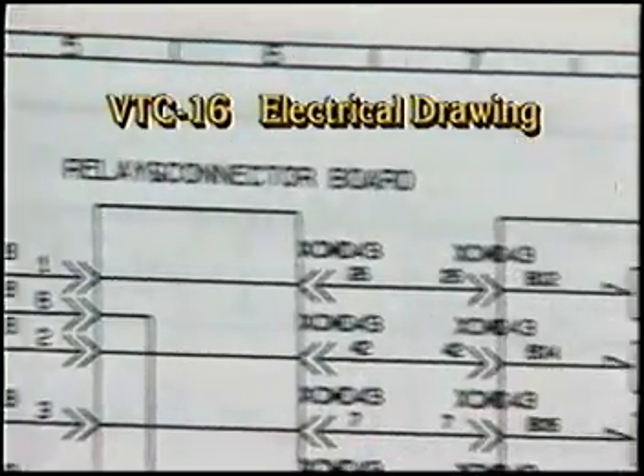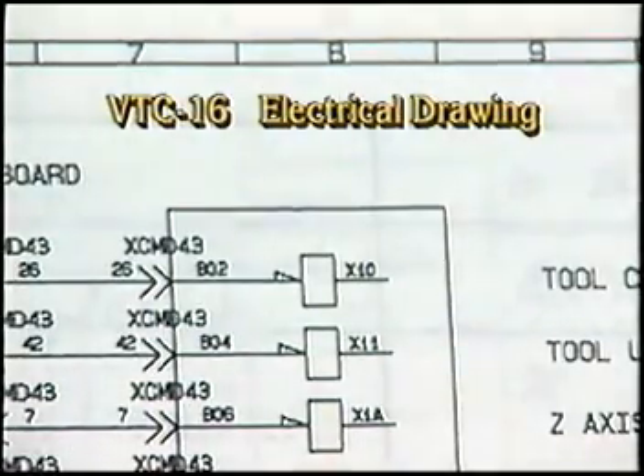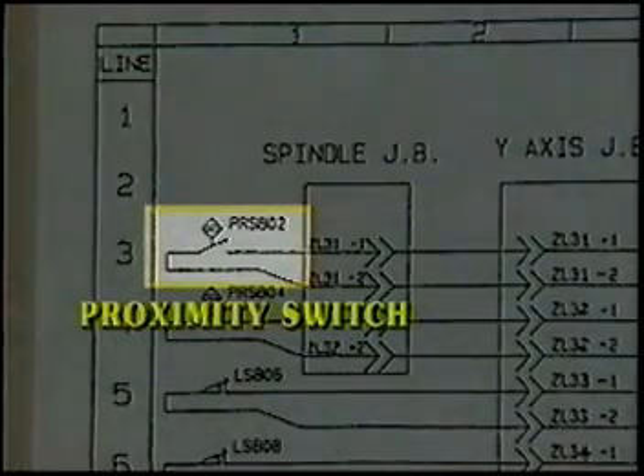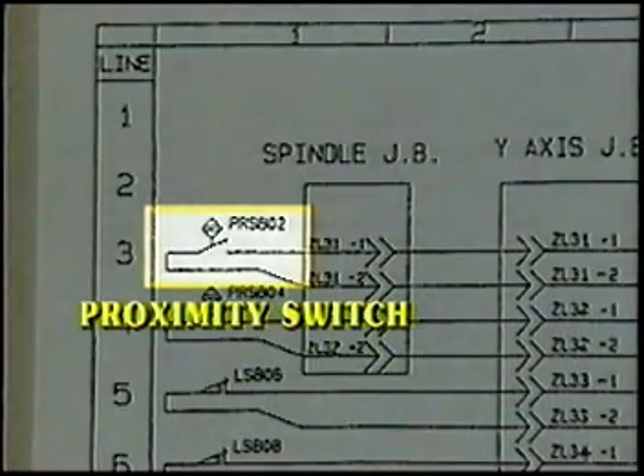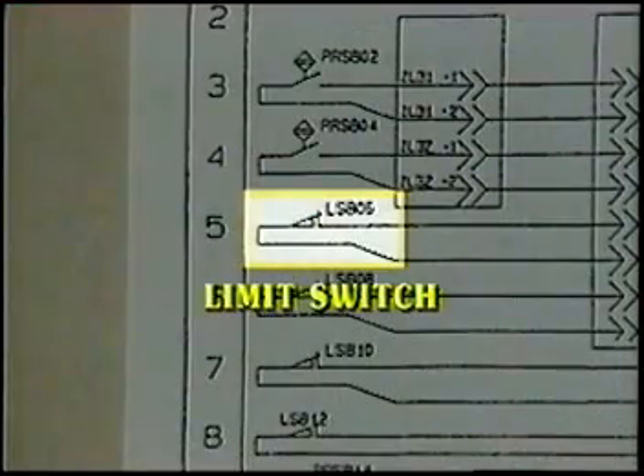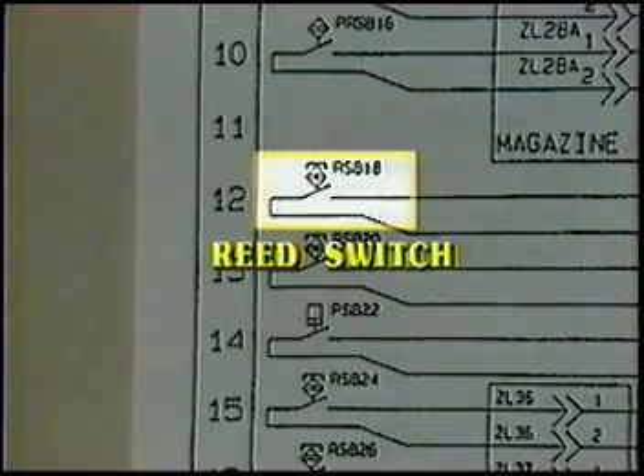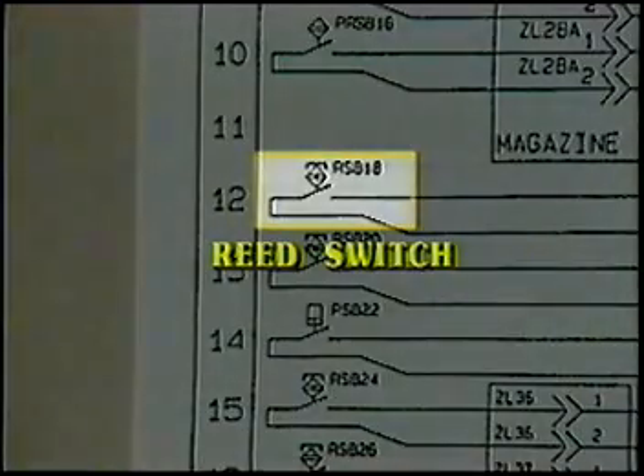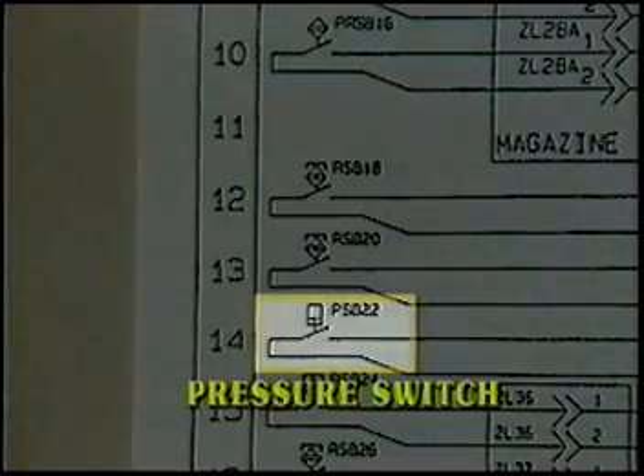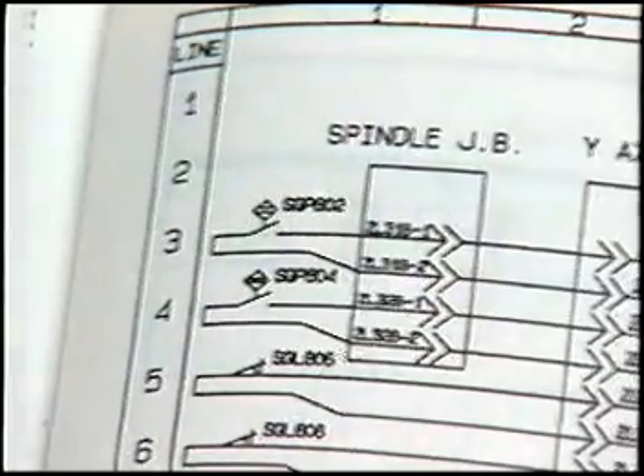Here is a sample of the electrical drawing for the VTC-16. The symbols used are also shown in the maintenance guide. This is a proximity switch. It senses metal and is used to confirm an operation. This is the symbol for a limit switch such as the X, Y, and Z axes limit switches. Shown here is a reed switch used on the air cylinder. Here is the symbol for a pressure switch.